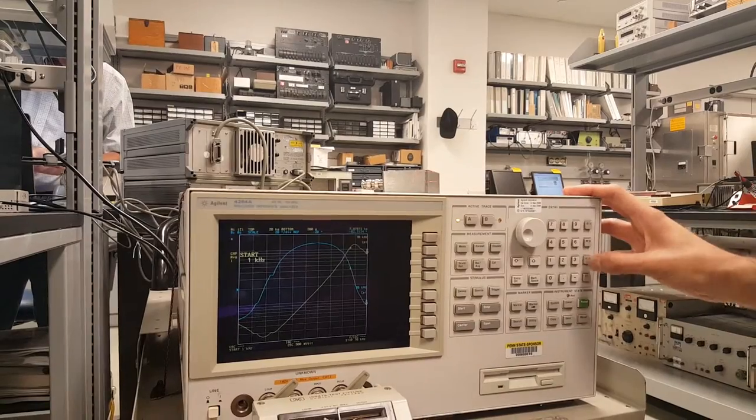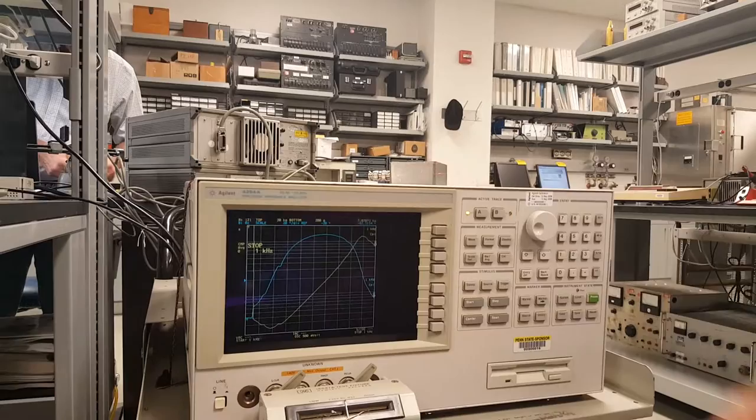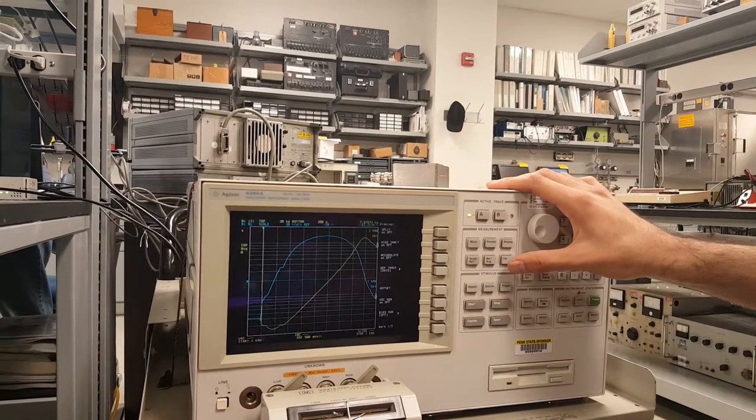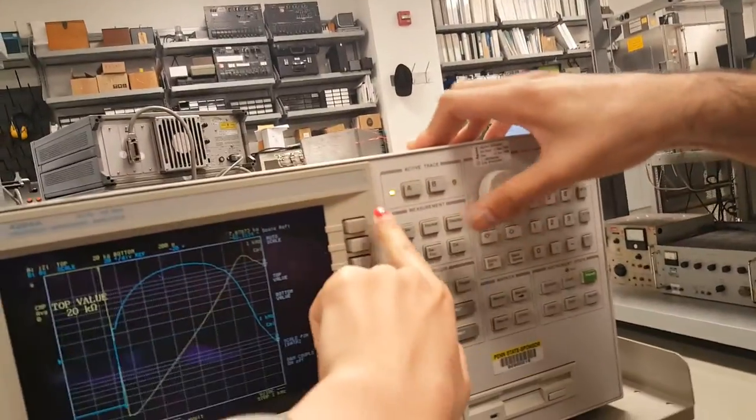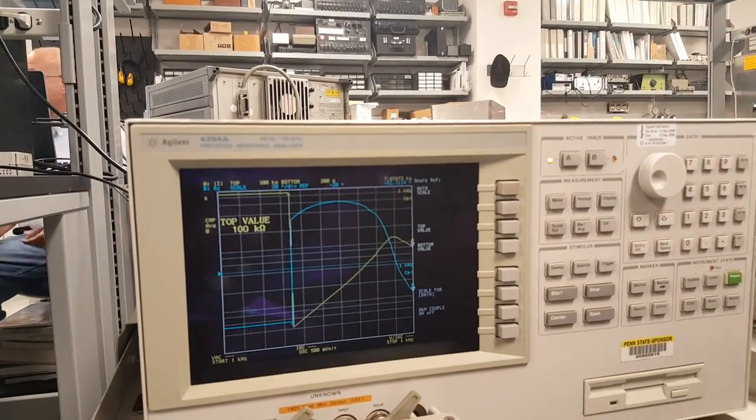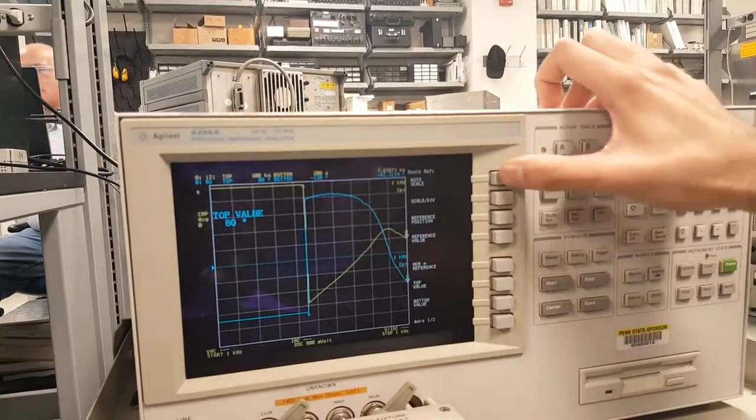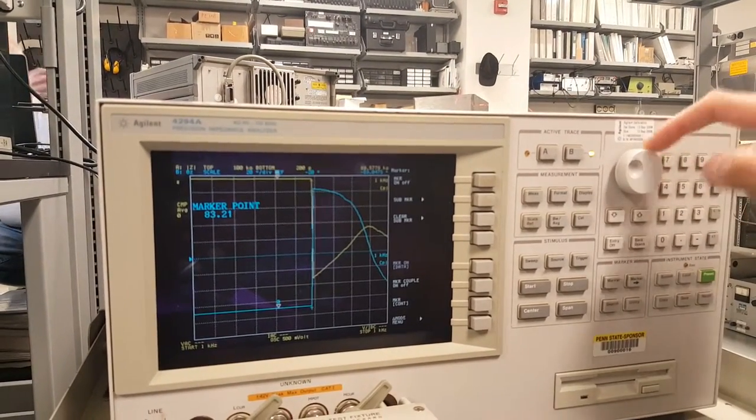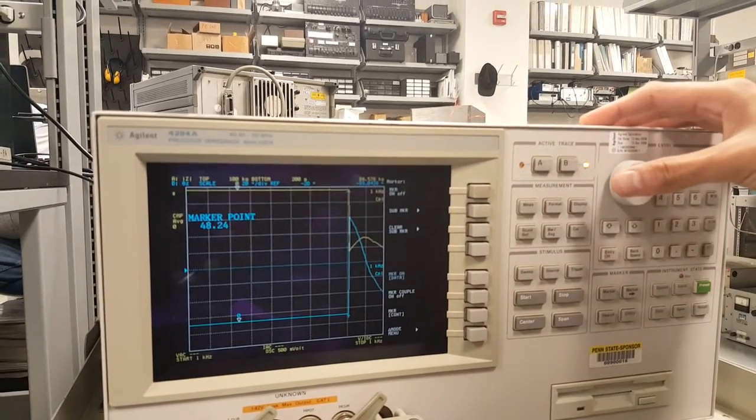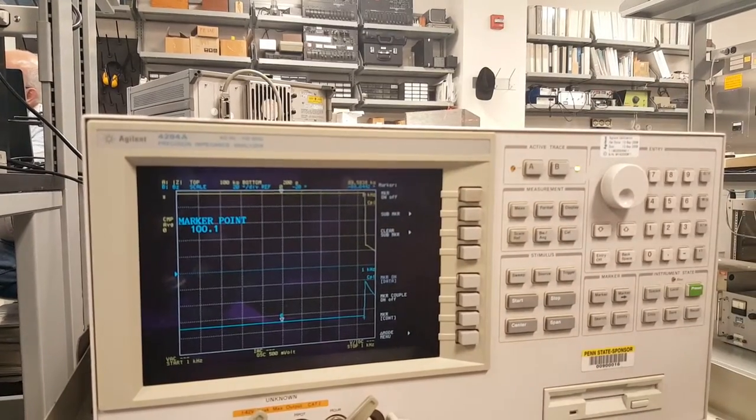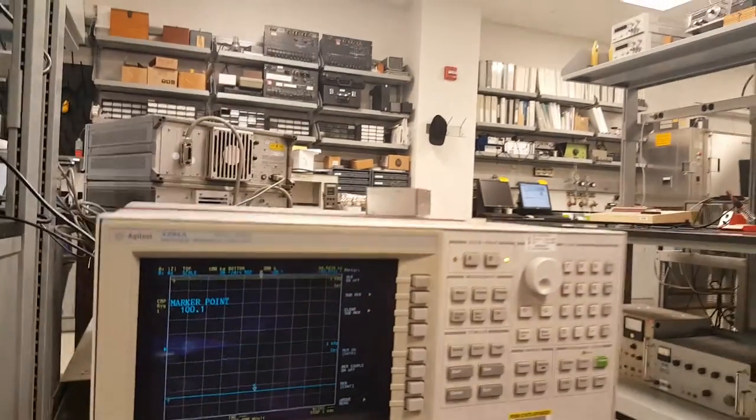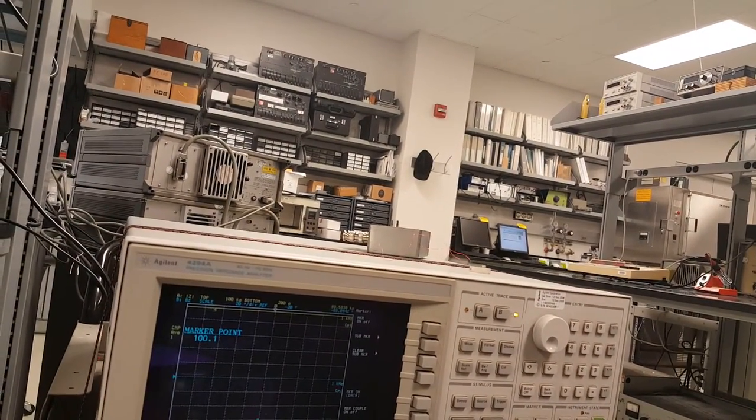So, the easy way I mentioned. It can be start one kilohertz. Stop one kilohertz. And you might have auto scale. Display? Where's auto scale again? You can auto scale A and B. It seems taking a while. But it doesn't make a difference. Let's take the marker. And let's go back here. Now we can tell. So the off-resonance, so once it completes we can just take the data. See what the phase is. Remember from the phase you can get the tangent delta prime. You know that now.